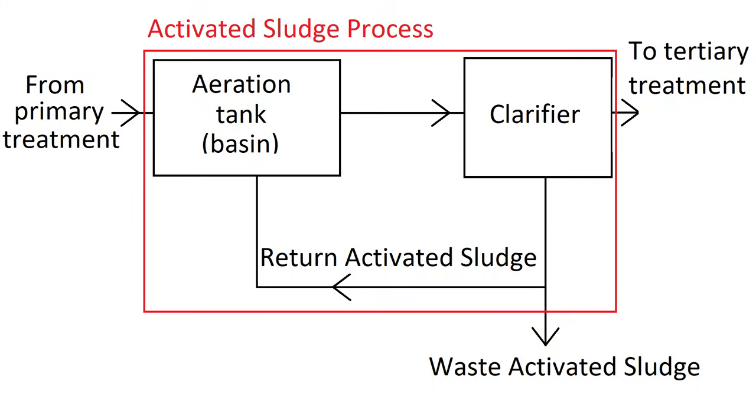The sludge handling is a little bit more interesting though. Some of the activated sludge is removed from the clarifier, stabilized, and then disposed of off-site. There are several possibilities for its ultimate destination, with direct application to farmland as fertilizer, incineration, and landfilling being the most common. Because this sludge is discarded as a waste product rather than used in the process, it's called waste activated sludge, or WAS, and the process of pumping it away is called wasting.